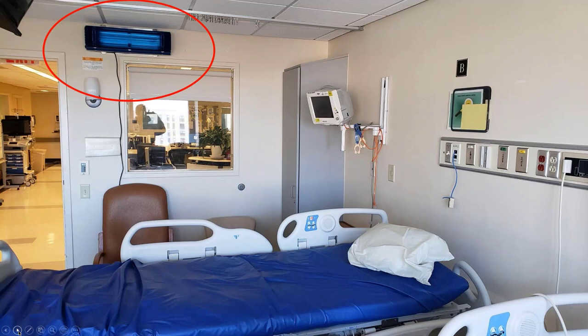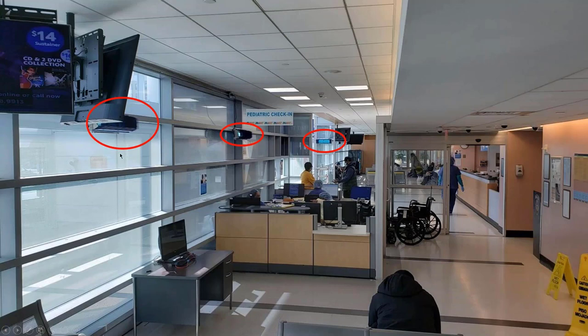They can be in the room with the patient, above their head, so it's something that can be on all the time, 24/7, in patient rooms. They can also be in lobbies, especially in hospitals where they're triaging people or people are coming into the emergency room, just trying to disinfect that air. Think about a hospital room having 6 air changes an hour, meaning every 10 minutes that air is flushing out of the room and past these lights through the air handling unit. And remember, that air handling unit doesn't only service that one patient room—it services multiple patient rooms on that floor, unless it's an isolation room.